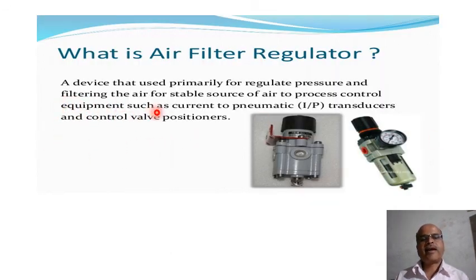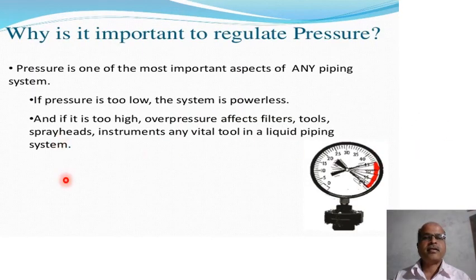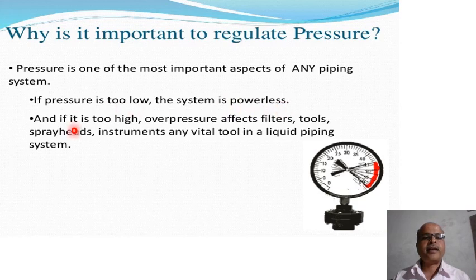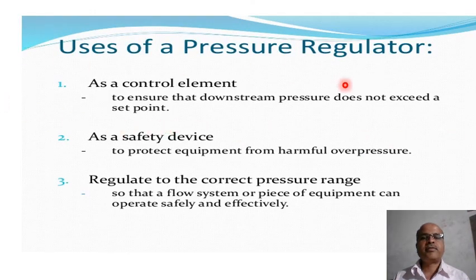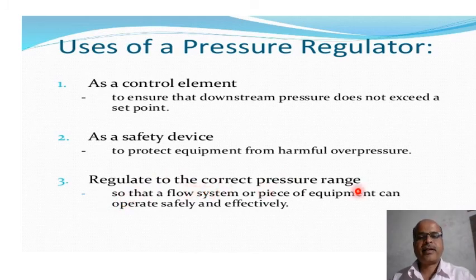An air filter regulator is a device used primarily for regulating pressure and filtering air for a stable source of air to process control equipment such as current-to-pneumatic transducers, control valves, and positioners. Pressure regulation is important because if pressure is too low, the system is powerless, and if it is too high, over-pressure affects filters, tools, spray heads, and instruments. Uses of a pressure regulator include: ensuring downstream pressure does not exceed a set point, acting as a safety device to protect equipment from harmful over-pressure, and regulating to the correct pressure range.